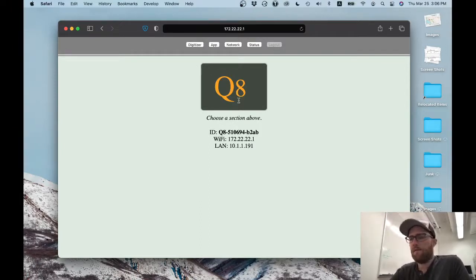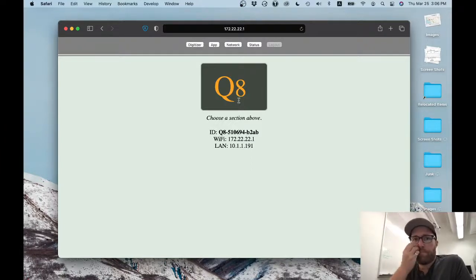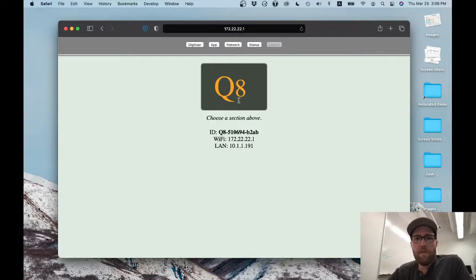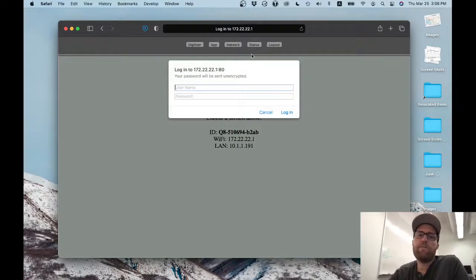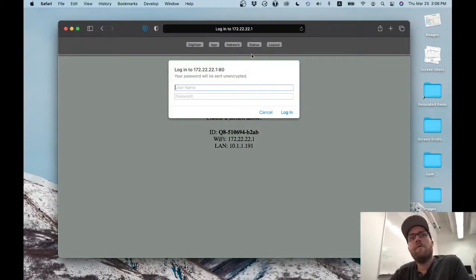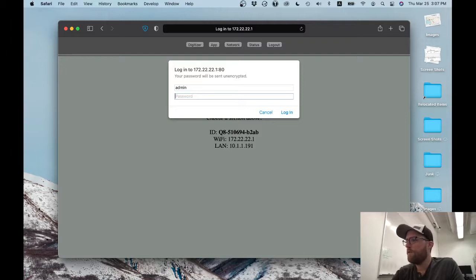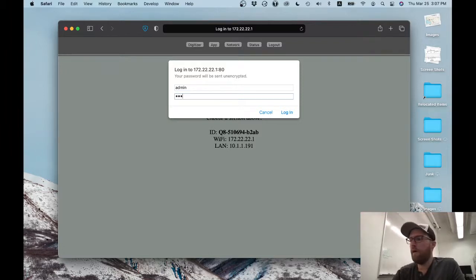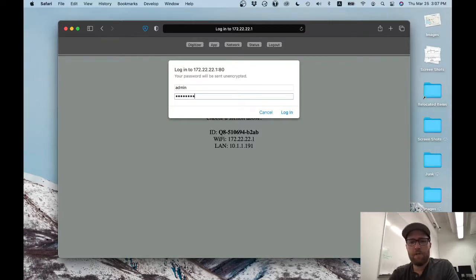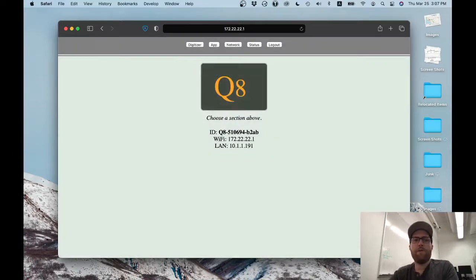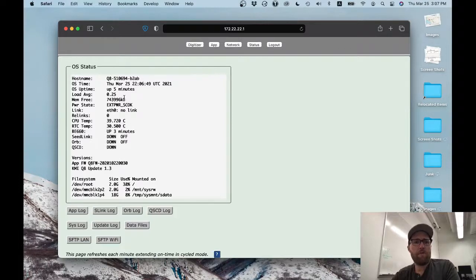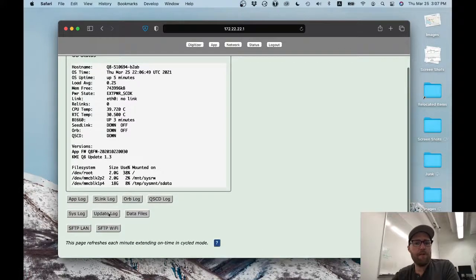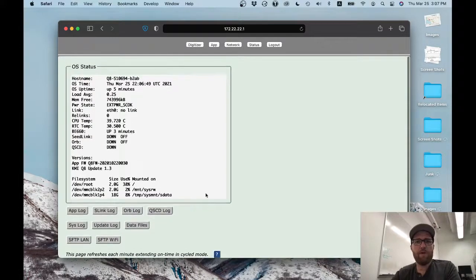Let's try that. 172.22.22.1. There we go. So, this is the Q8's web interface. And this is how we configure it, view its status, everything. Let's see what happens when I click status. Okay, so it's password protected. Username is admin. Again, this was all in the reference guide. The default password is just KMI and then the serial number. So, in this case, it's KMI510694. Certainly, we want to change all these passwords before we send this out into the field.